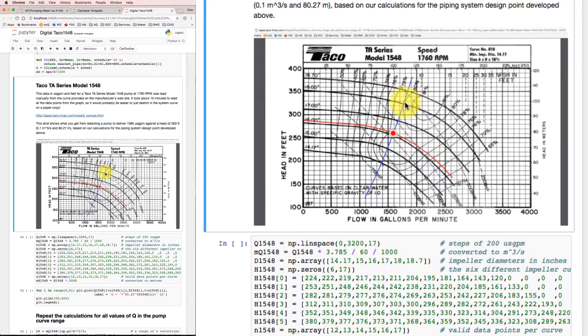Now they've drawn this blue line on here and that blue line was based on the assumption that all of our head requirements were frictional losses. So this line if we followed it down here would eventually as a parabola intersect with zero somewhere down here. But in fact about half of our head rise has to go for the 40 meters of elevation change. So the blue line that it should have drawn should have started about here and gone up in a parabola something like that. So if we want to use this information we're going to probably have to draw our own blue line.